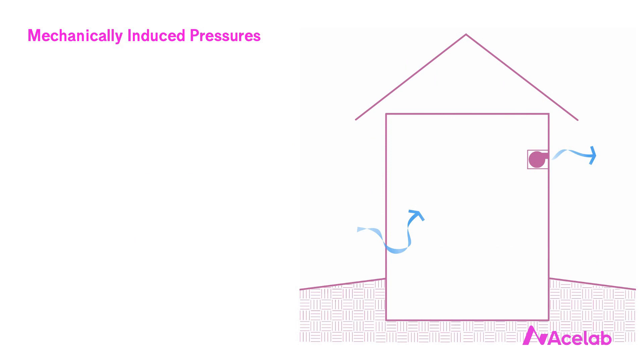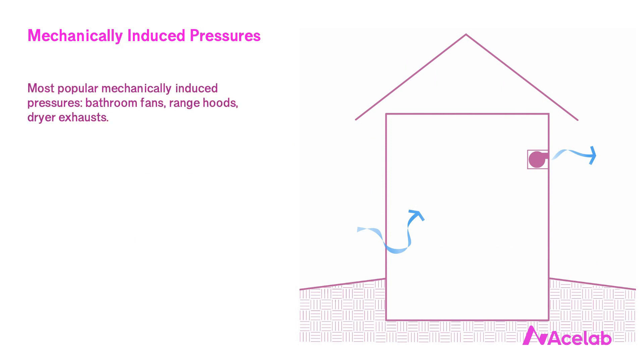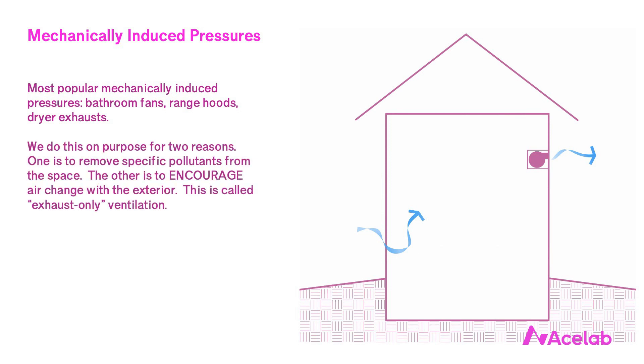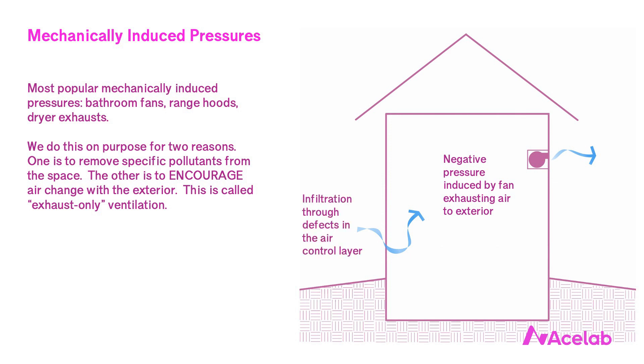The third way to create pressure differences in buildings is to mechanically induce them. The most common sources are bathroom fans, range hoods, and dryer exhausts. We create these pressures on purpose for two reasons: to remove specific pollutants from the space, and to encourage air change with the exterior — this is called exhaust-only ventilation. It works by using a fan to exhaust air from a space, which causes the space to become negatively pressurized, inducing infiltration through defects in the air control layer to compensate. Air out equals air in.